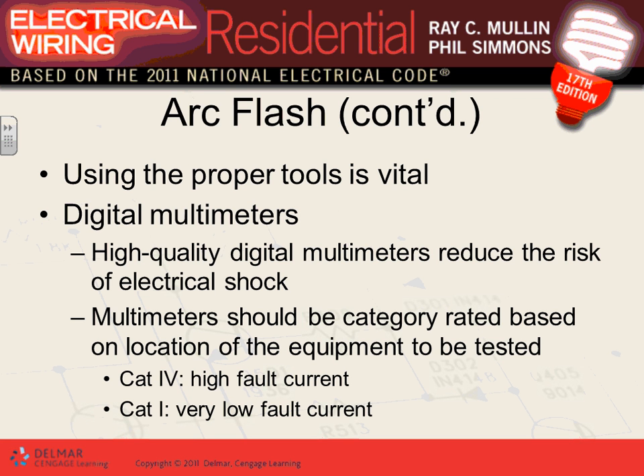But if the plier you're working with is $10, a fully insulated one is $20, double the amount. Insulated means that when you grab that plier, the handle is fully insulated to handle 600 volts, and they have versions for 600 volts and higher, fully insulated. The ones we use here with you guys are not—they're called comfort grip. They're just for your hand to feel good. They're not meant to go torque something energized.